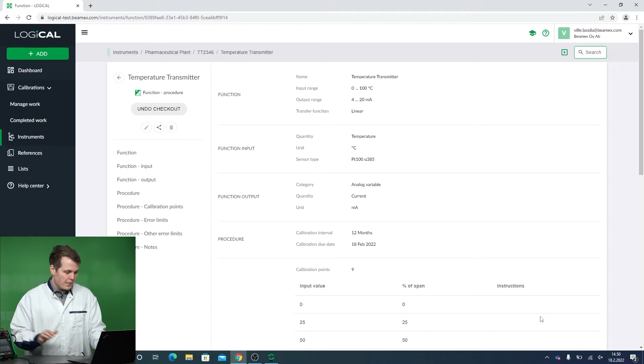I will check this out, and once it's checked out, I need to transfer the calibration job to the actual MC6. To do this, I will head out to the Logical Sync application and click on Synchronize. Now it is sending the calibration job from the cloud to the MC6. And once it has done that, we can head out to the MC6.